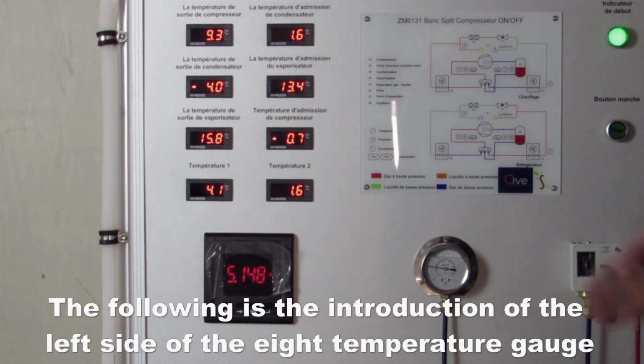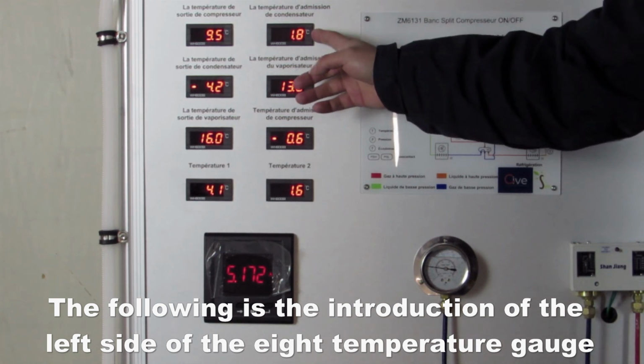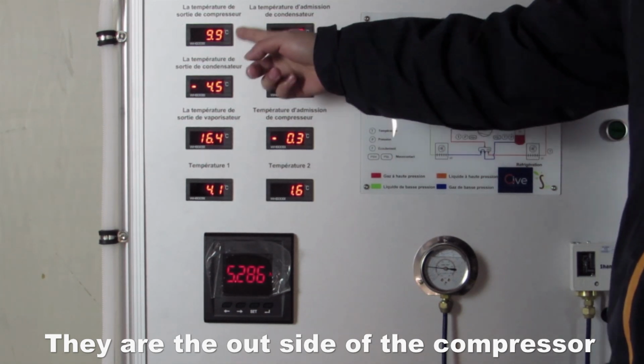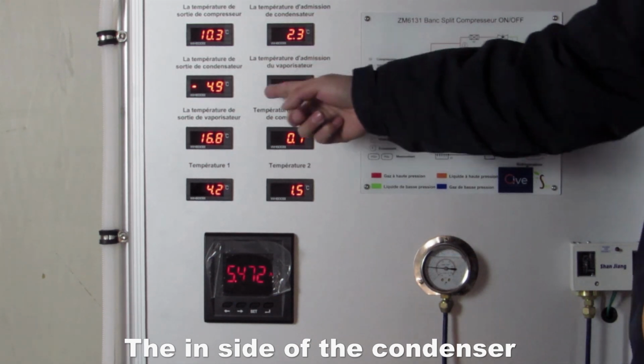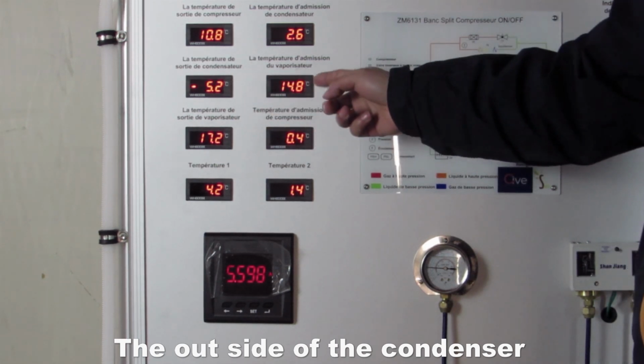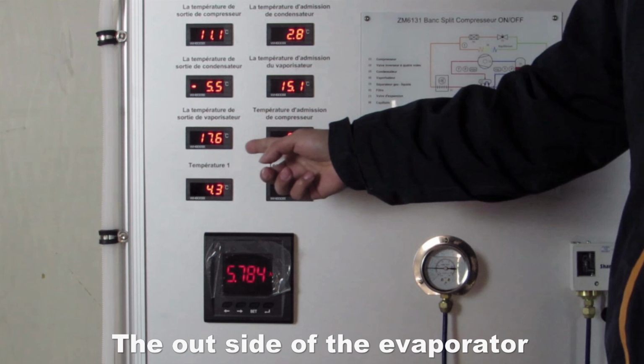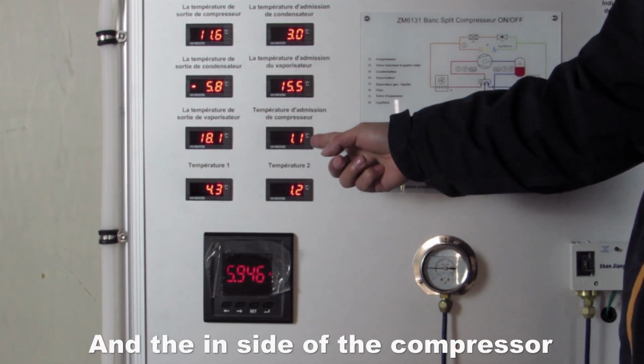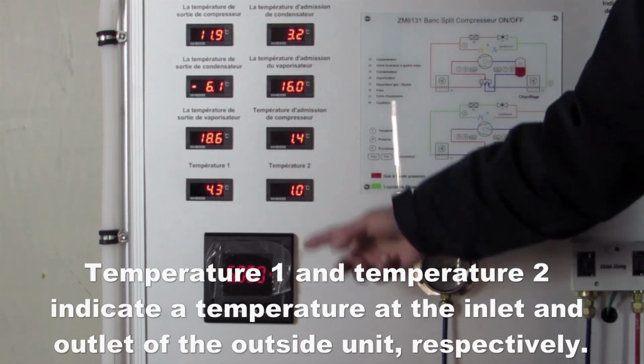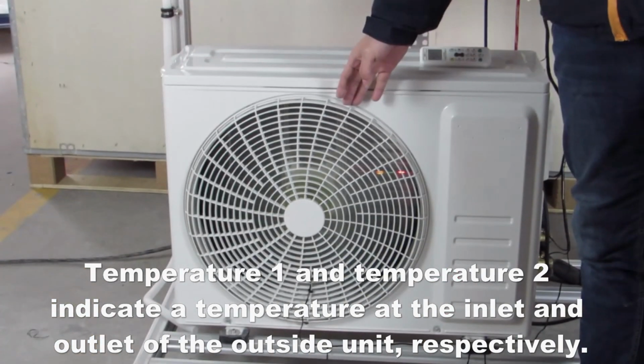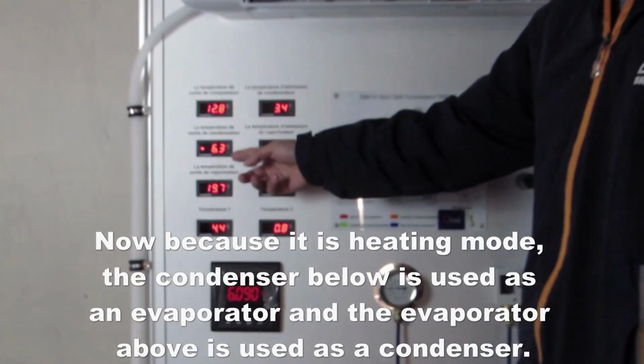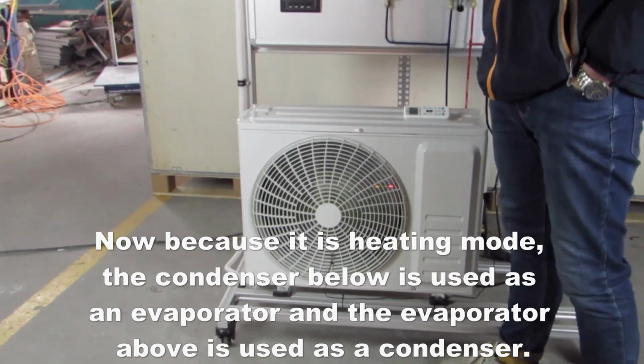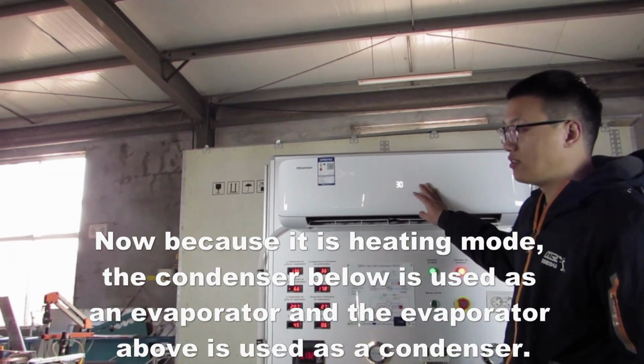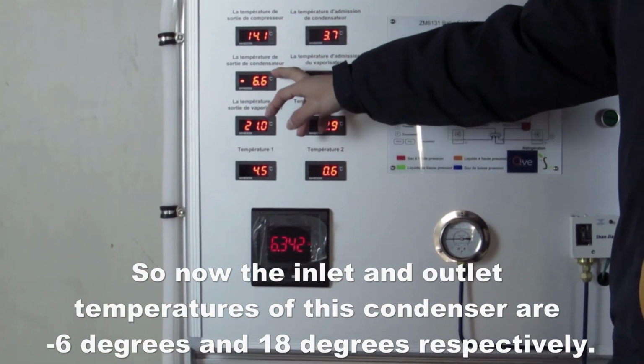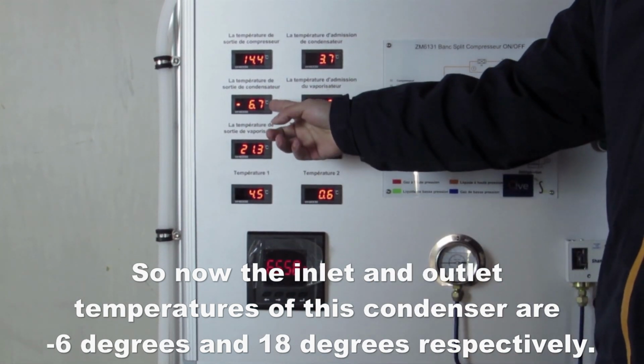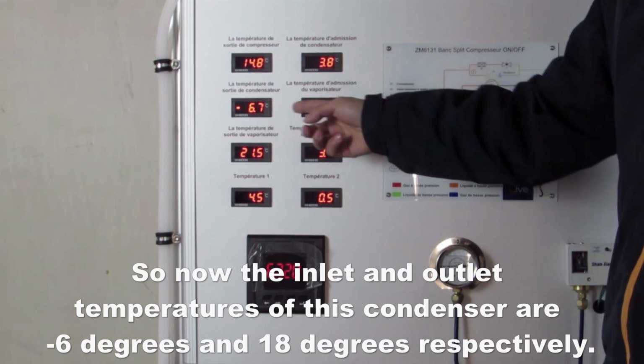The following is the introduction of the left side of the eight temperature gauge. They are the outside of the compressor, the inside of the condenser, the outside of the condenser, the inside of the evaporator, the outside of the evaporator and the inside of the compressor. Temperature 1 and temperature 2 indicate the temperature at the inlet and outlet of the outside unit. Now, because it is heating mode, the condenser below is used as an evaporator, and the evaporator above is used as a condenser. So now the inlet and outlet temperatures of this condenser are -6 degrees and 18 degrees respectively.